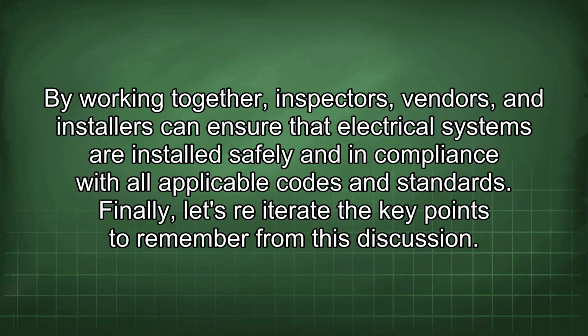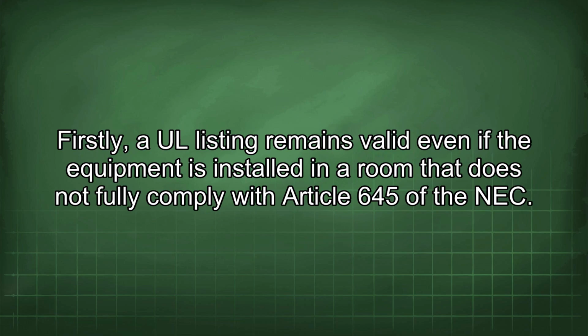By working together, inspectors, vendors, and installers can ensure that electrical systems are installed safely and in compliance with all applicable codes and standards. Finally, let's reiterate the key points to remember from this discussion. Firstly, a UL listing remains valid even if the equipment is installed in a room that does not fully comply with Article 645 of the NEC.